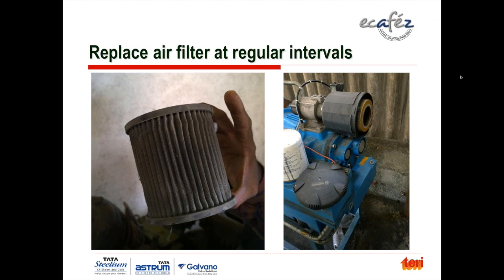Now moving on, I'll give you another example of where one can save energy even without a single rupee of investment. Every air compressor has an air filter, like most engines. Simply by cleaning the air filter at regular intervals, you reduce the pressure drop across the air filter and save energy. Every air compressor manual gives recommendations on when to clean the air filter, but the rule of thumb is every 15 days to take out the air filter and clean it with compressed air or a handheld blower. It can be used to save energy very simply in the plant.